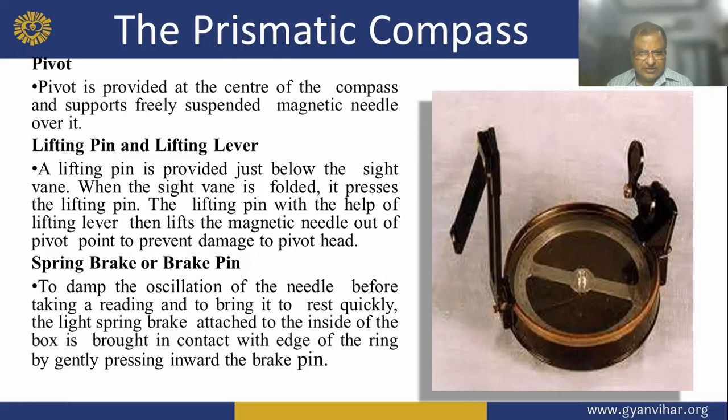Now, the spring brake or brake pin. It is used to dampen the oscillation of the needle before taking the reading and to bring it to rest quickly. The light spring brake attached inside the box is brought into contact with the edge of the ring by gently pressing the brake pin.